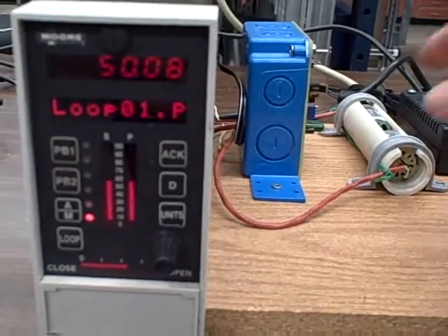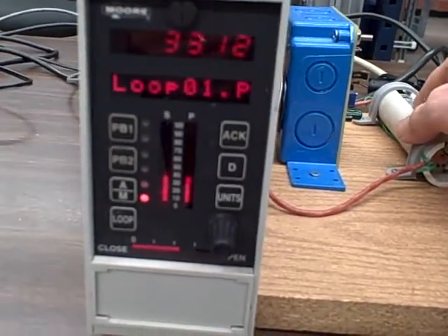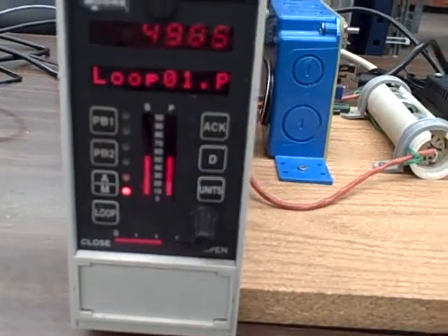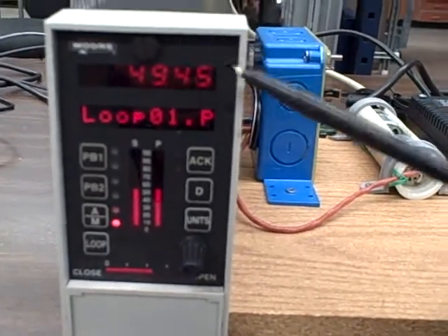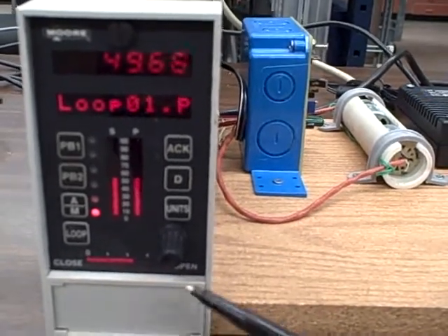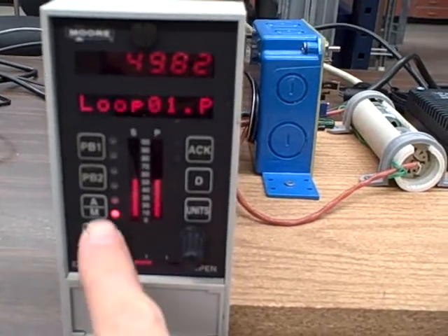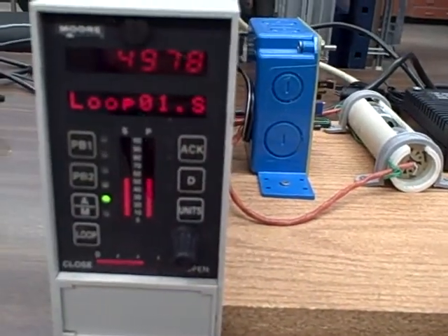If I were to load down the motor with my finger, the controller takes no corrective action whatsoever. It's in manual mode, so it will ignore any changes in the process variable. It will display what the process is, but it will take no effort to correct it or to maintain it at set point.